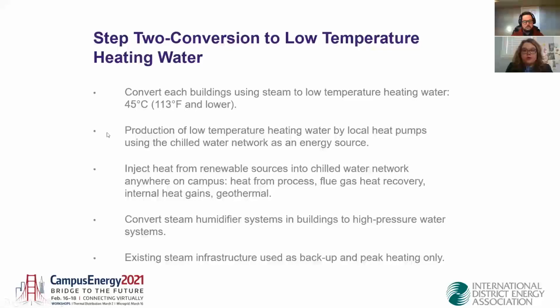So that low temperature water is produced by local heat pumps that use the chilled water network as an energy source. So how do we get that energy? Well, in winter, a measure that's often done is free cooling in ventilation systems. So we're stopping that free cooling and doing mechanical cooling. So that means that heat that's in the building, instead of being thrown out, is thrown in that energy network and is being recovered by heat pumps. So in time, we will inject heat from renewable sources into that chilled water network.